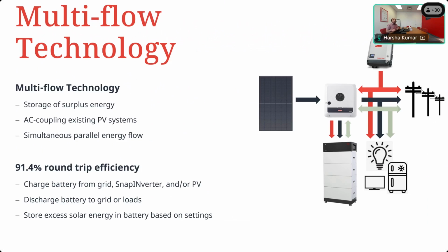Now that you're making your own grid, that grid interface is good enough for the two 10K Primos, the older style units, which means previously when hydro went down, those two 10Ks would have gone down too, but now they won't, because the Gen24 becomes the grid when hydro is down. This means the PV array feeding the other two 10K inverters can potentially be used to charge the battery via the Gen24.